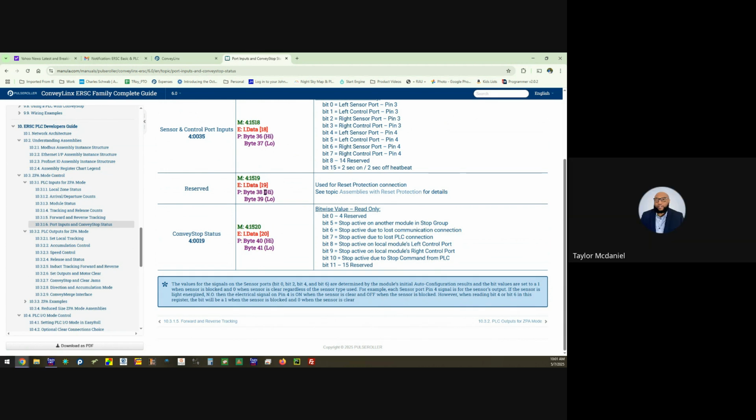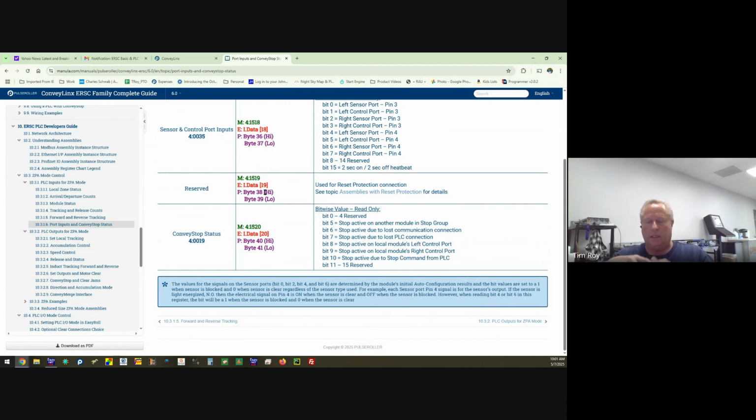But the PLC said it accumulate. Why, what's going on here? Well, it was because of all the startup. The PLC's faster than the cards. So what they developed was reset protection. And it requires 3 steps. Step 1.